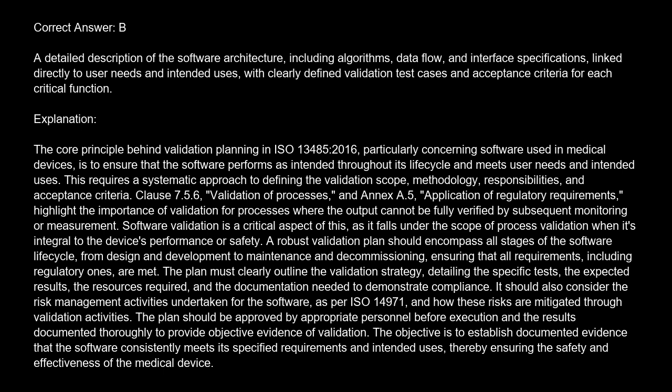This requires a systematic approach to defining the validation scope, methodology, responsibilities, and acceptance criteria. Clause 7.5.6, Validation of processes, and Annex A.5, Application of regulatory requirements, highlight the importance of validation for processes, where the output cannot be fully verified by subsequent monitoring or measurement.